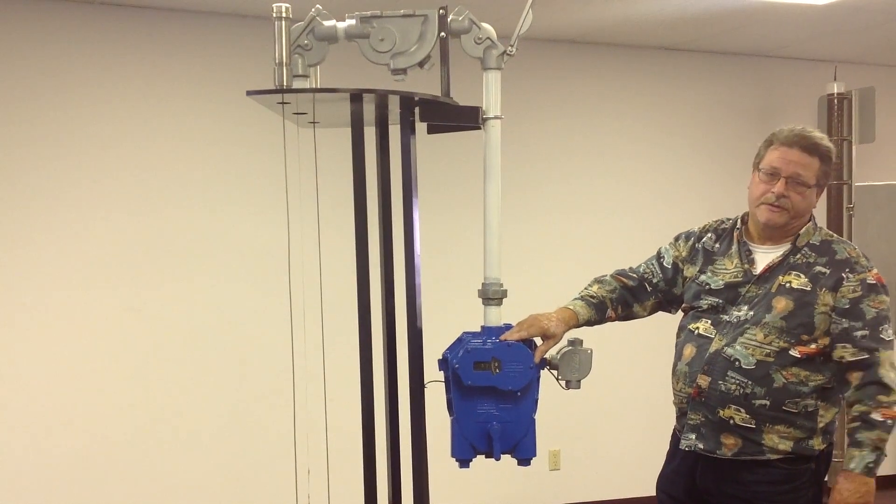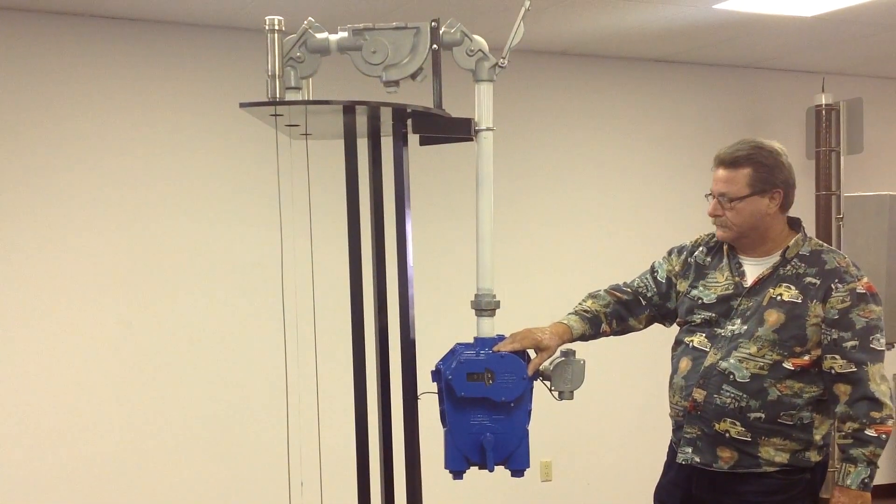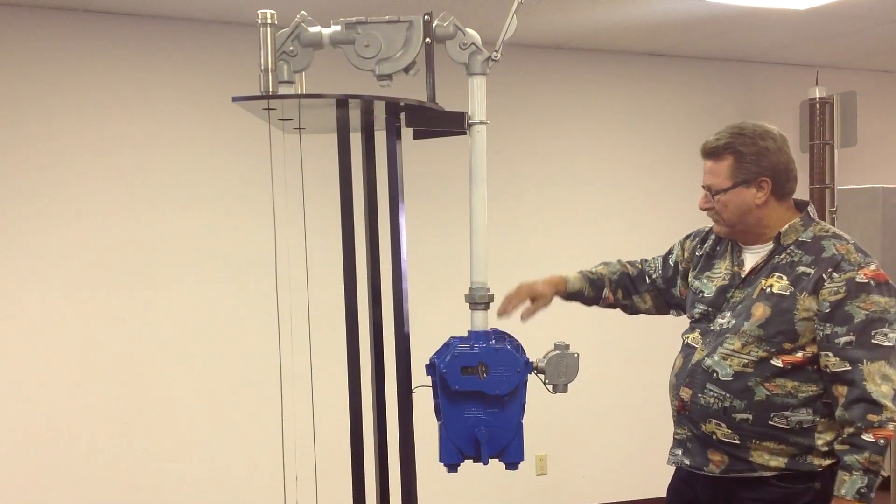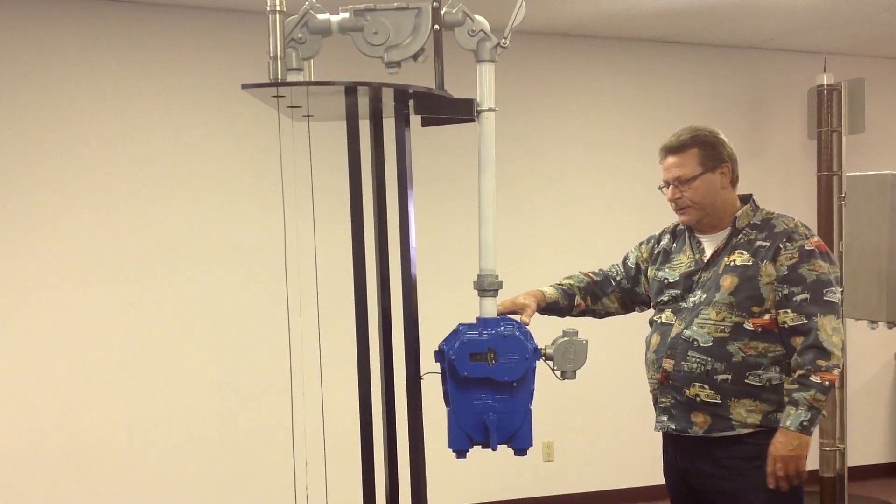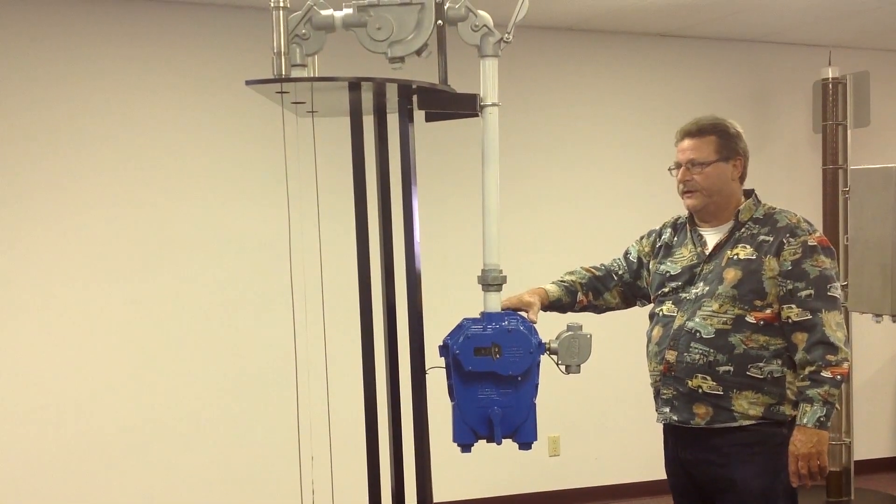This unit is also known as the mechanical tape and float gauge. You have a mechanical readout on the front. Electronics can be purchased separately to add to the back to send information to your PLC or to your computer.